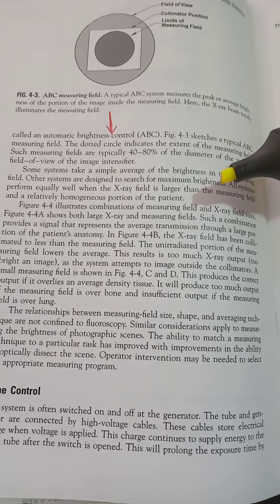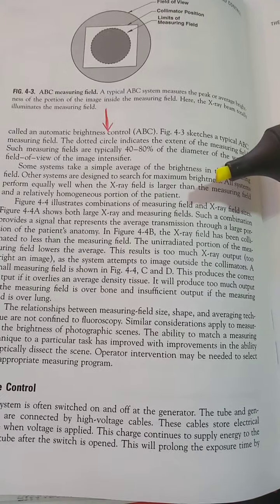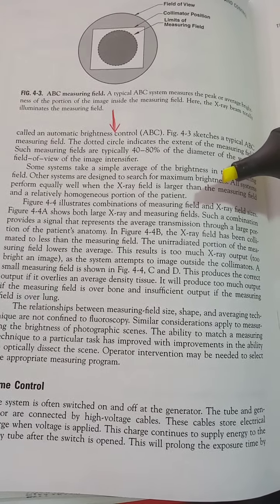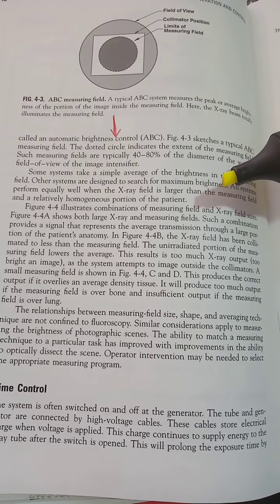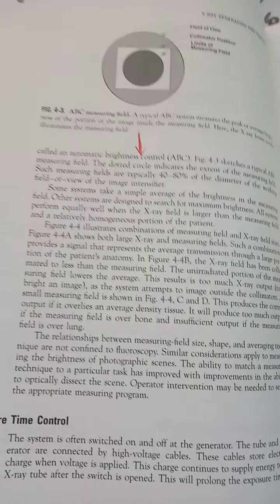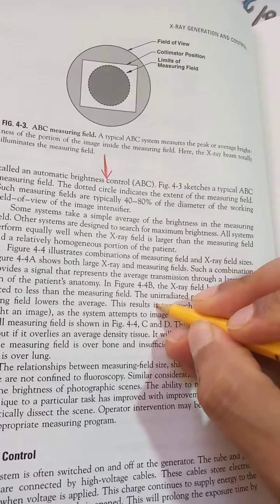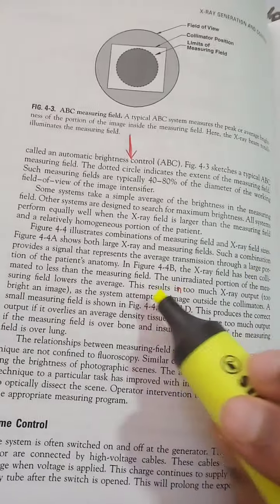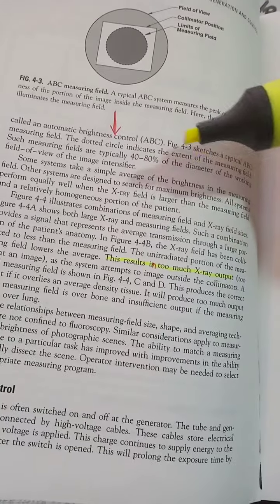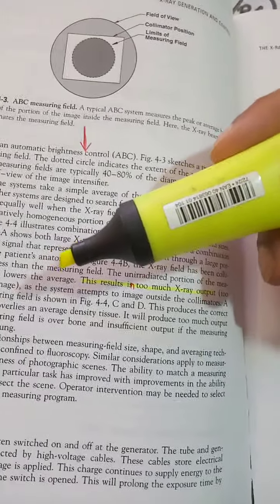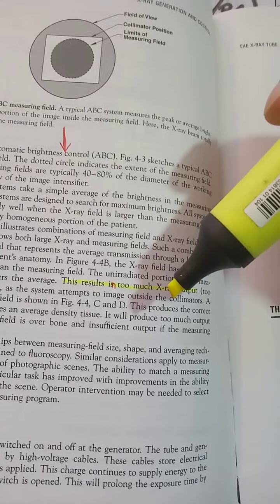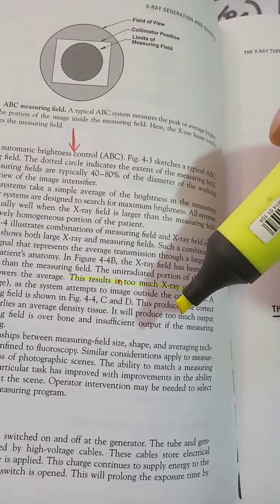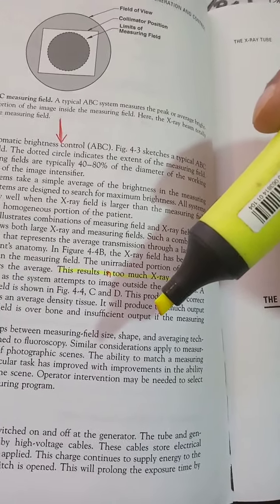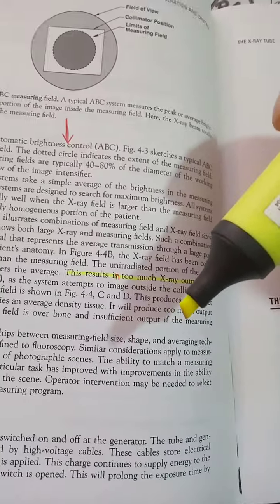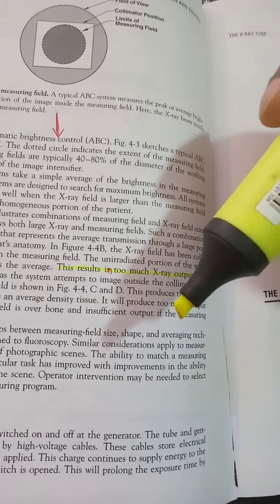The B would show the X-ray field collimated to less than the measuring field. The unirradiated portion of the measuring field lowers the average. This results in too much X-ray output, because of a hyper bright image, as the system attempts to image outside the collimators. A small measuring field in C and D produces the correct output if it overlies an average density tissue, like muscle. It'll produce too much output if the measuring field is over the bone, and insufficient output if measuring over the lungs.